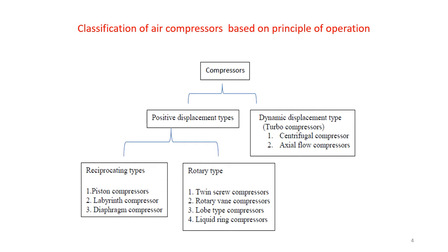So the compressors are classified as positive displacement type compressors and dynamic displacement type or turbo compressors. Under positive displacement we have reciprocating type compressors or rotary type compressors. Under dynamic displacement type we have centrifugal and axial flow compressors. In the majority of pneumatic applications, the positive displacement types are more important. So we will focus our discussion on this particular type of compressor.